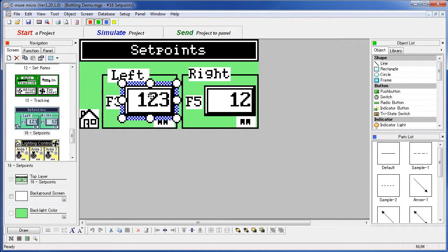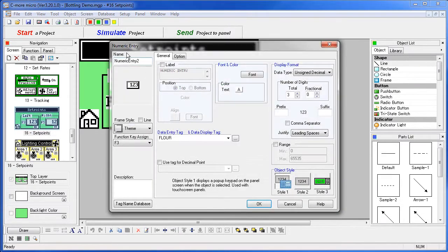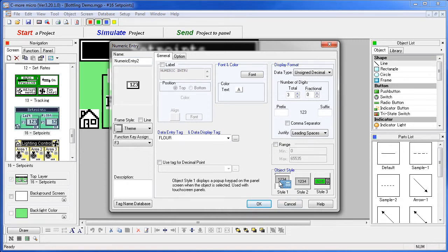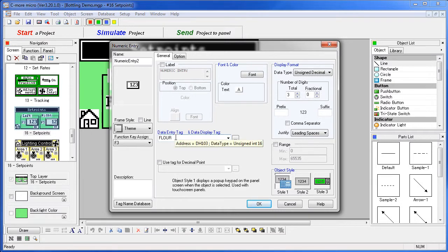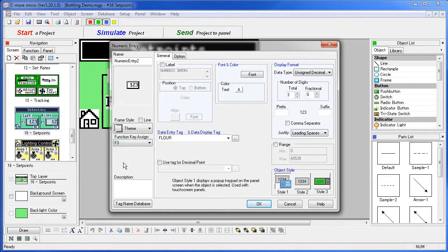This button is a numeric entry button. The key point here is it's using object style 1. That gives us the touchscreen pop-up keypad. It's also limiting the number of digits to 3, it's controlling the FLOUR tag, and can be activated by using function key 3.